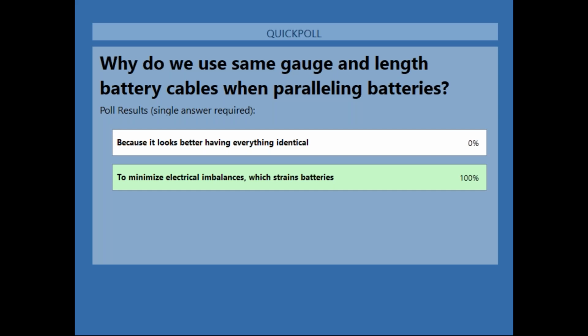One rule is using the same gauge wire and the same length, which helps minimize imbalance. I'm glad everybody already realizes that, so we'll go into more detail. The more batteries you have in parallel, the greater the risk of a connection problem, as we've mentioned. Same size wire and length will help minimize that imbalance.